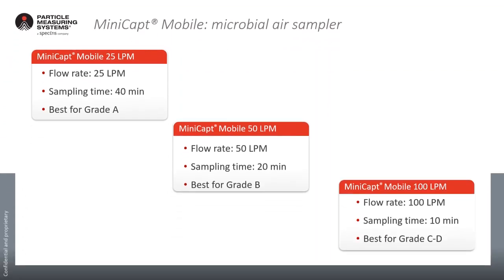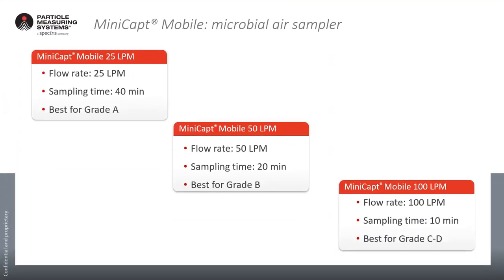Thank you, Mark, for that great presentation. I will now ask Julia to talk about our BioCapt and MiniCapt mobile instruments. The MiniCAP mobile is available in three different flow rates: 25, 50, and 100 liters per minute, which allow you to choose the best solution based on your specific needs. One of the most important parameters to consider when choosing the most appropriate flow rate is the grade of your clean room in which you perform the sampling.